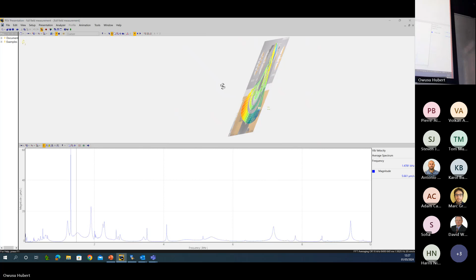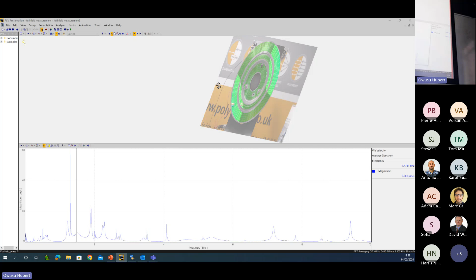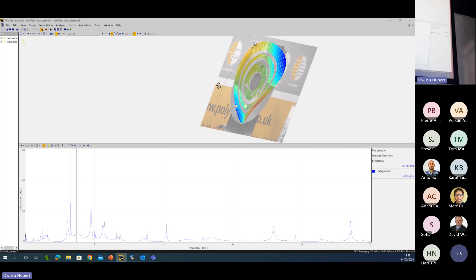So upon measuring your specimen, or the brake disc in this case, you have a spectra. This is your operational deflection shape data, and this is not your modal analysis. And therefore it's really important to have this, which sometimes you just use a vibrometer to do, but this one works out your angles for you. The computer calculates your angles for you, so you don't need to calculate your X, your Y, and your Z coordinates. It works out the distance, how far the sensor head was from the brake disc. It worked that out for you, and already you have an idea how the brake disc is behaving.